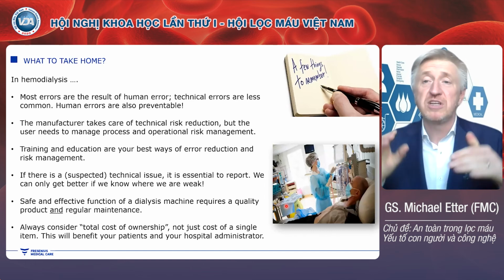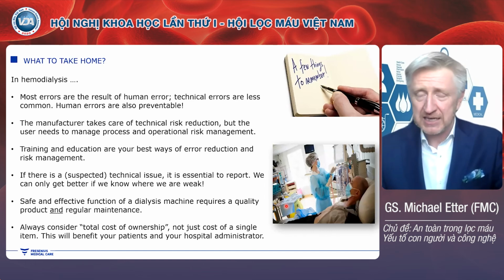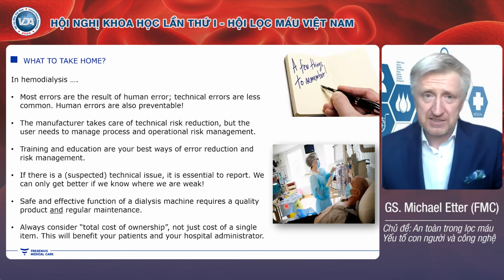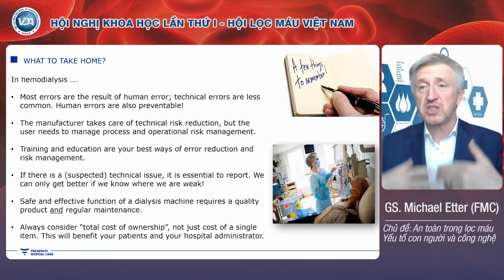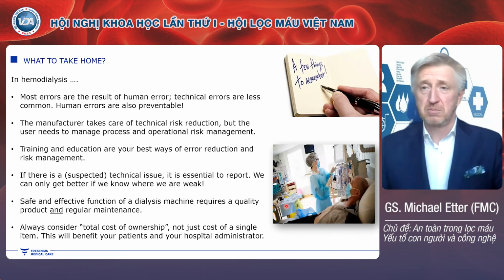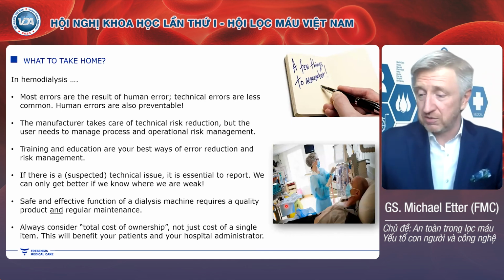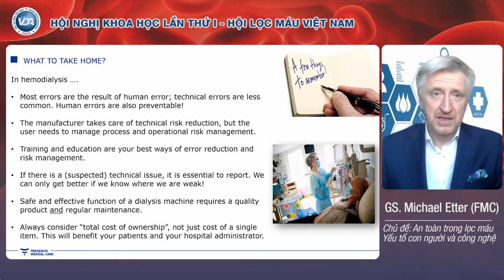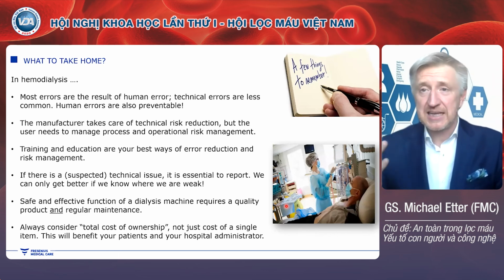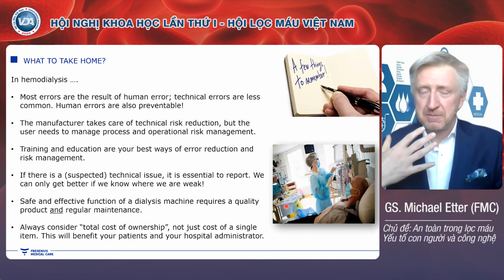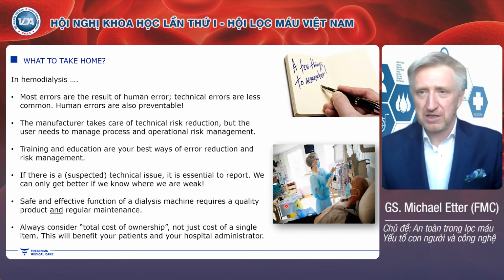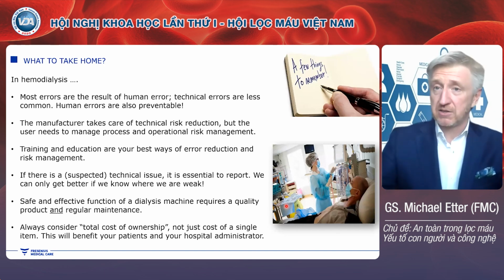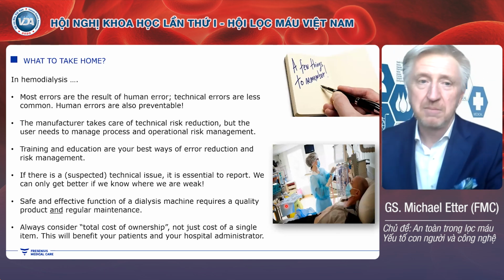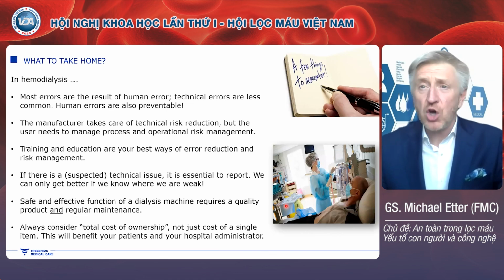We manufacturers take the responsibility to reduce the technical risk as much as we can. That's why I showed you all these safety features that are in the machines. But it's also the operator who needs to have good processes in place to make sure that the operation of the machine is safe. If there is a suspected technical issue, and I showed you examples where something can go wrong, let the manufacturer know. It is very important that you report this. Report it through the mandatory channels. It can be the regulators, health authorities, but also inform the manufacturer, because we can only get better if we know where we are weak.